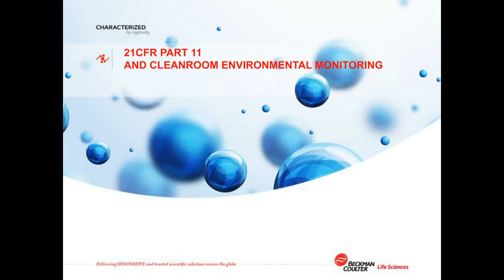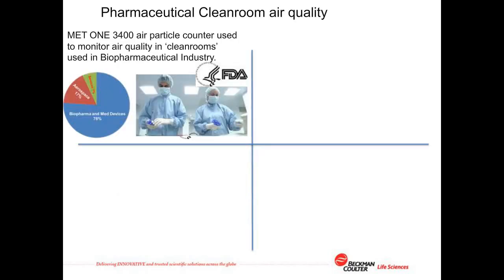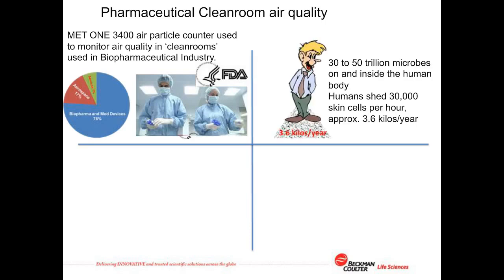So that's the ALCOA guidance from the FDA. Let's take a look at this in the context of pharmaceutical clean room environmental monitoring. The FDA mandates that air quality conditions for pharmaceutical production should maintain certain air quality. The real danger is not particulates in the air in the clean room, but in fact the microbes on the human body. Humans shed around 30,000 skin cells per hour, all of which are potentially carrying microbes. Unfortunately, we don't have a technology available today which can detect these microbes in real time, so that's why we use air particle counters. In fact, the human body sheds approximately 3.6 kilos of skin per year.